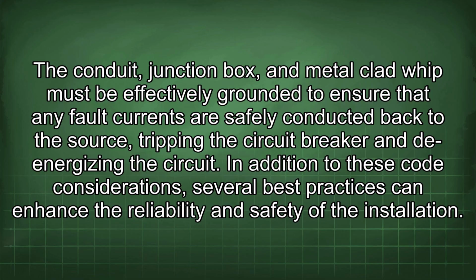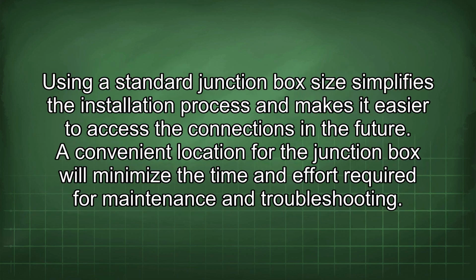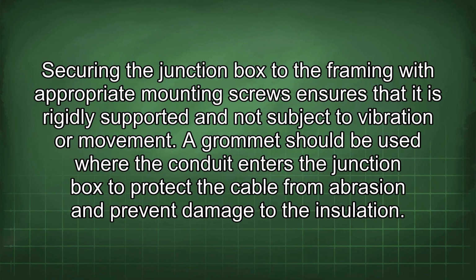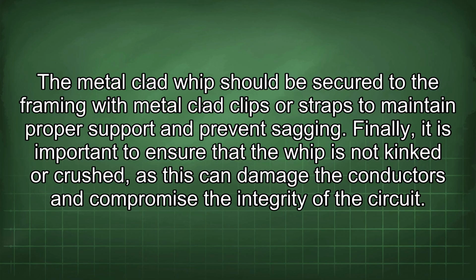In addition to these code considerations, several best practices can enhance the reliability and safety of the installation. Using a standard junction box size simplifies the installation process and makes it easier to access the connections in the future. A convenient location for the junction box will minimize the time and effort required for maintenance and troubleshooting. Securing the junction box to the framing with appropriate mounting screws ensures that it is rigidly supported and not subject to vibration or movement. A grommet should be used where the conduit enters the junction box to protect the cable from abrasion and prevent damage to the insulation. The metal-clad whip should be secured to the framing with metal-clad clips or straps to maintain proper support and prevent sagging.